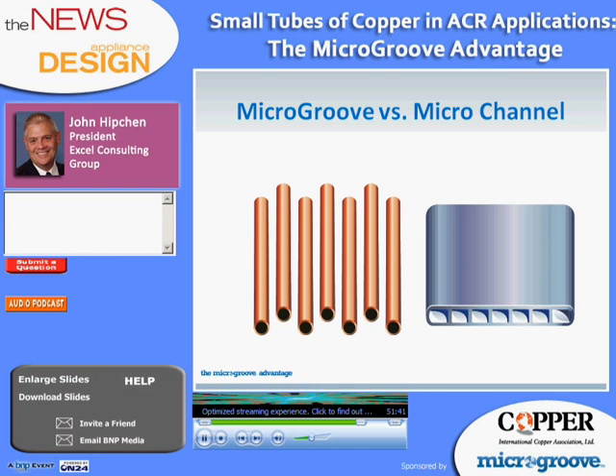Okay, another question. Does the refrigerant type being used matter to the tube diameter that's being used in a coil? No, the small diameter tubes are more desirable actually as operating pressures increase. Higher pressures typically are required to condense refrigerants such as R410A or R744 compared to refrigerants that have been phased out such as R22. So the working pressure is directly proportional to the tube wall thickness and inversely proportional to the diameter. So in other words, for tubes with the same thickness, smaller diameter tubes can withstand higher pressures than larger diameter tubes. So the refrigerant does not matter.